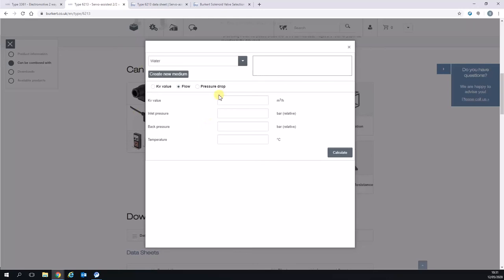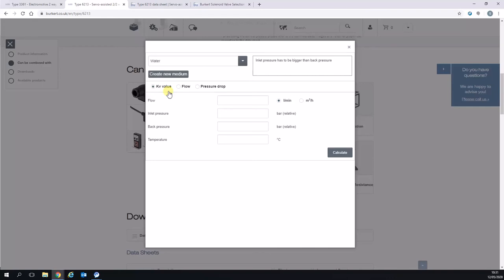We're going to use this in the first instance to calculate a KV. What a KV actually is, it's a flow coefficient factor that says you can put a certain volume of liquid through the valve at one bar pressure drop at 20 degrees Celsius. You'll also often come across CV, which is the US gallons per minute version at one PSI pressure drop. To get from KV to CV, we simply take the KV and multiply it by 1.11.